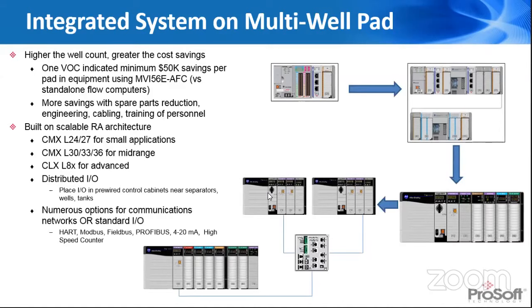Since everything's built in Studio 5000, a lot of the code developed on smaller systems can be migrated over into larger systems. So as the needs of their well pad site go from 6 to 12 to 18 or 24 wells, they can reuse some of that code. They can use add-on instructions that they've built and developed and migrate that into larger and larger platforms.